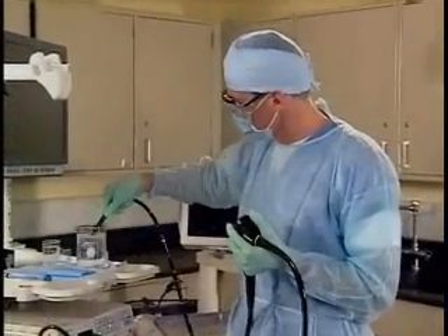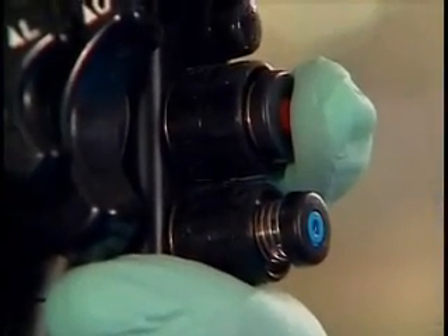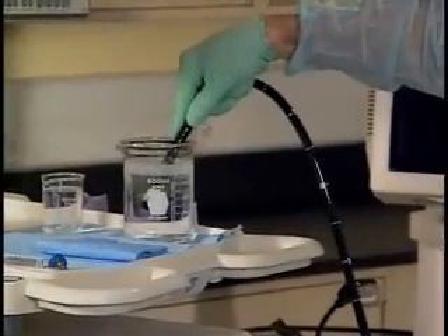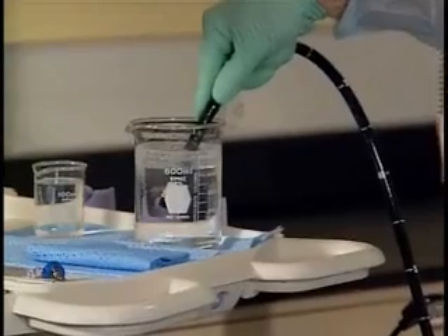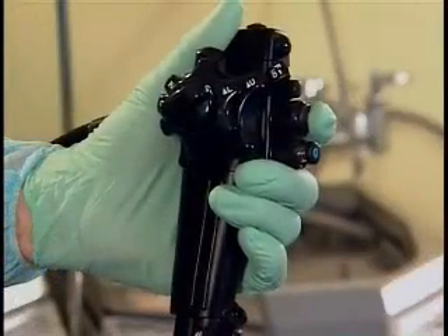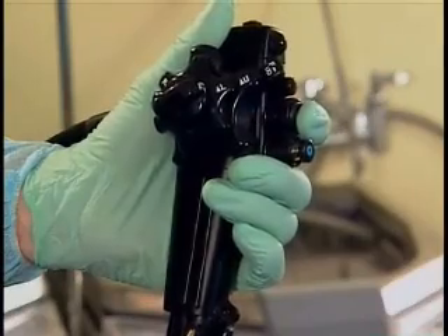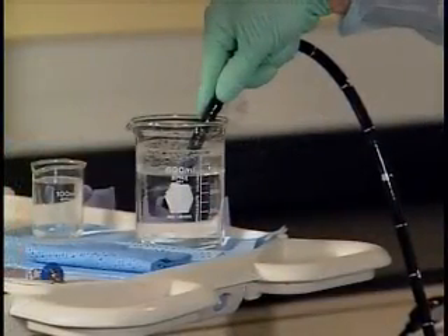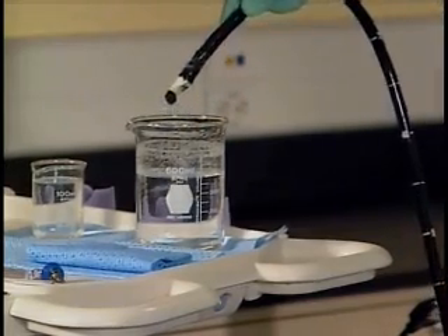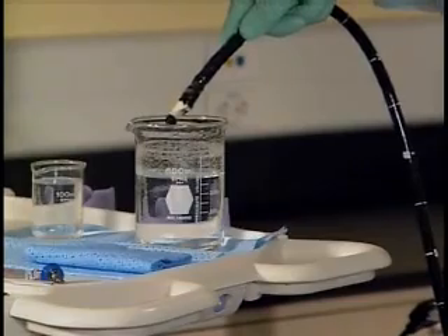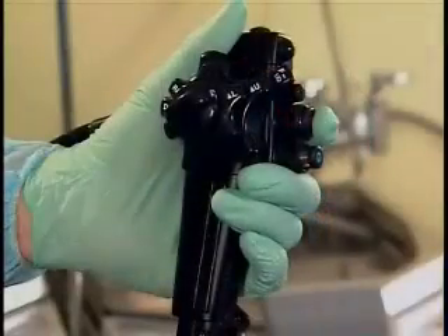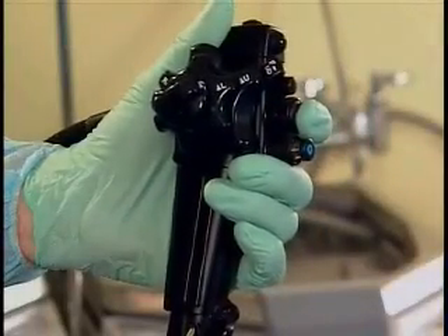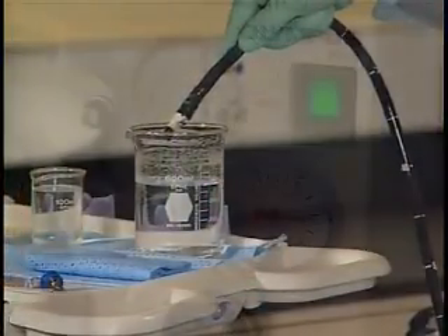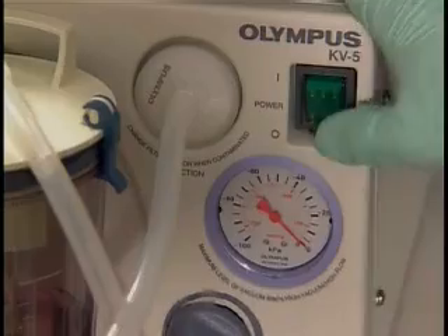Immerse the distal end of the endoscope in detergent solution. Depress the suction valve to the first stage and aspirate detergent solution into the instrument channel for 30 seconds. Then, depress the valve completely and aspirate detergent solution into the balloon channel for 30 seconds. Remove the tip from the detergent and aspirate air for 10 seconds through the instrument channel by depressing the valve to the first stage. Depress the valve completely and aspirate air through the balloon channel for 10 seconds. Now, turn off the suction pump.